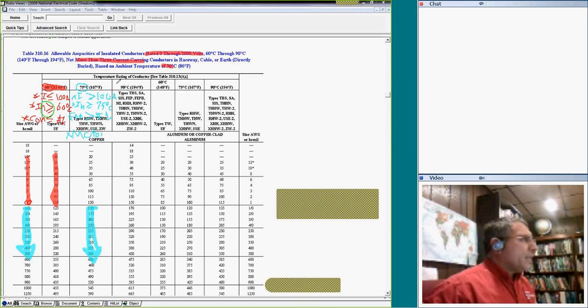The question would be then, Chad, when would we use a 90-degree column? To use the 90-degree column, guys, number one, I'm going to write it right here. Insulation must be equal or more than 90 degrees. If it's not equal or more than 90 degrees Celsius, don't even think about it. So that's rule number one.